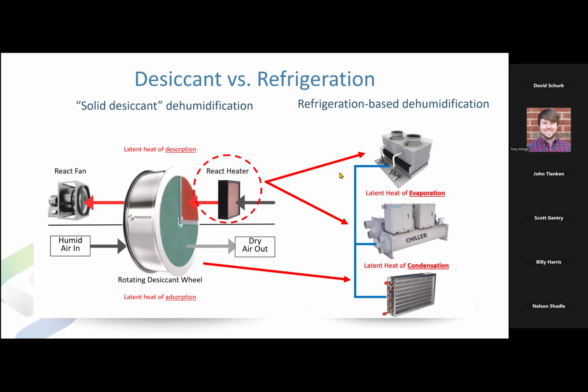So the parallel I want to draw is between my thermal energy input and the energy input required to drive a more traditional dehumidification system or air conditioning system, right? Now, as I mentioned, there is no free thermodynamic lunch. I have to create a thermodynamic difference between indoors, where I want to remove something, and outdoors, where I want to get rid of it. I have to create lift between the indoors and the outdoors. I do it with heat, with thermal energy. Gas, electric, steam, hot water, waste heat, doesn't matter. I have an energy input.